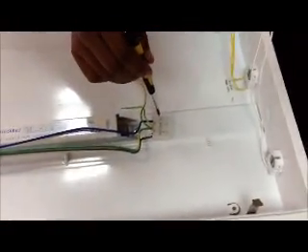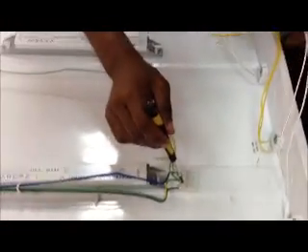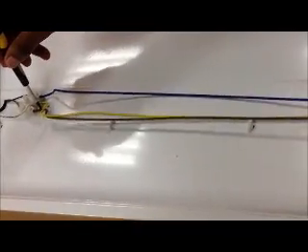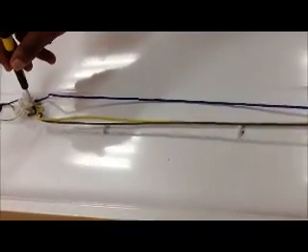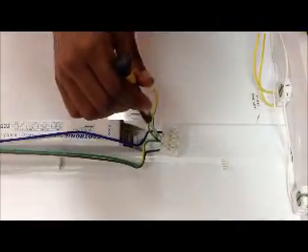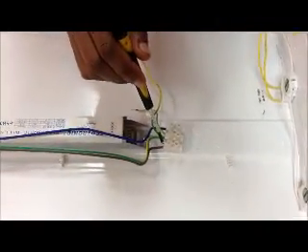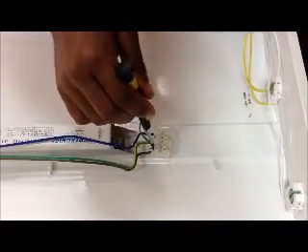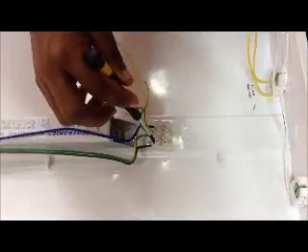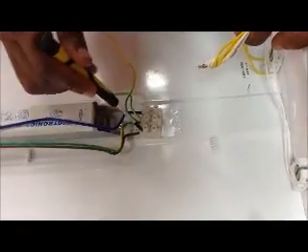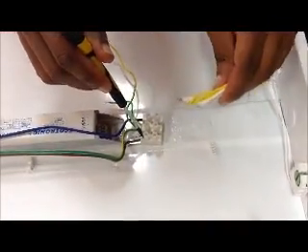So remember we have connected the other side to the blue wire which come to here. So we cannot connect this side to the blue wire as well. We have to connect it to the brown. Because you would have traced on this side the brown wire, the incoming brown is connected to the brown wire on this side. So we want to ensure that this brown wire is now connected to this side of the lamp. So we identify which bar connector the brown wire is connected to. We realize that this is the one that the brown wire is connected to. So I am going to put the junction that I have just created into this bar connector that the brown wire is connected to.